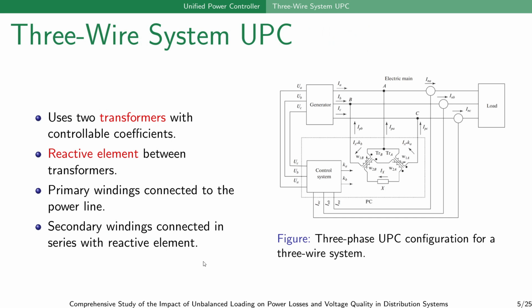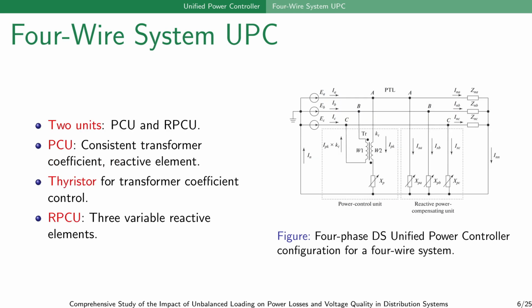In three-wire system, UPC three-wire system utilizes two transformers with controllable coefficient and reactive element placed between them. The primary winding are connected to power line, while the secondary winding are connected in series with the reactive element. This configuration helps to manage power flow effectively.